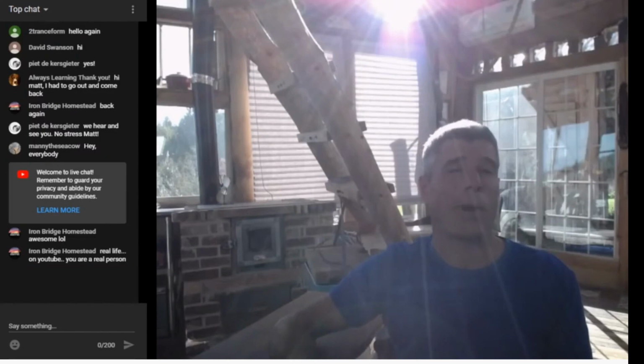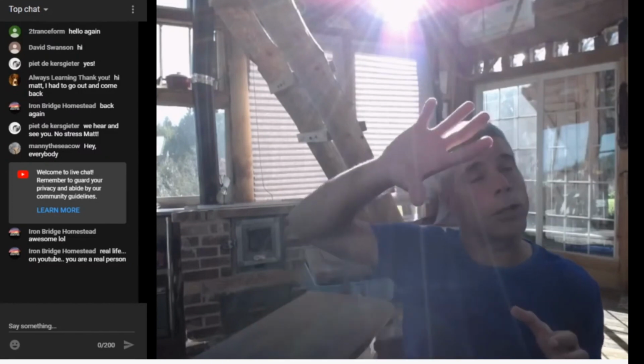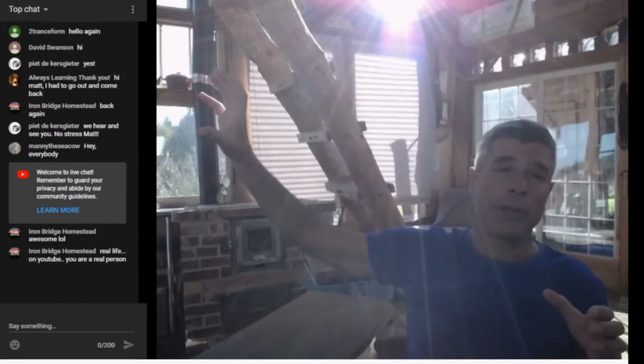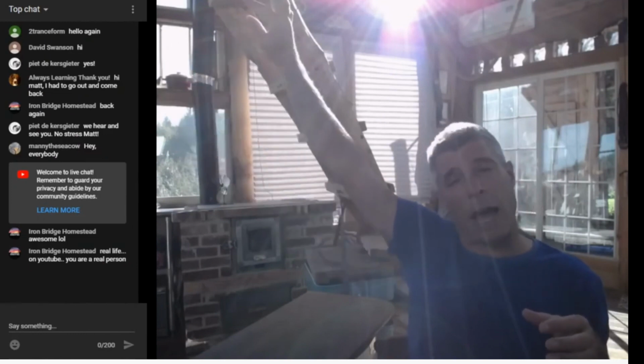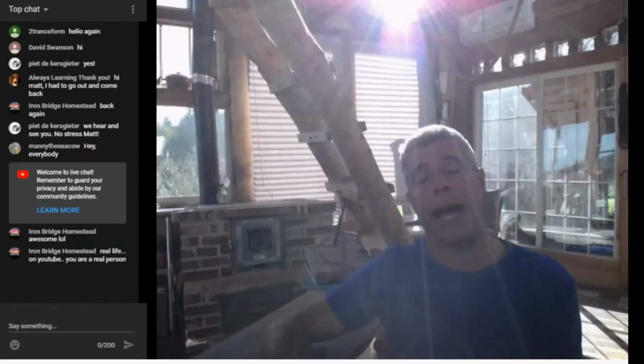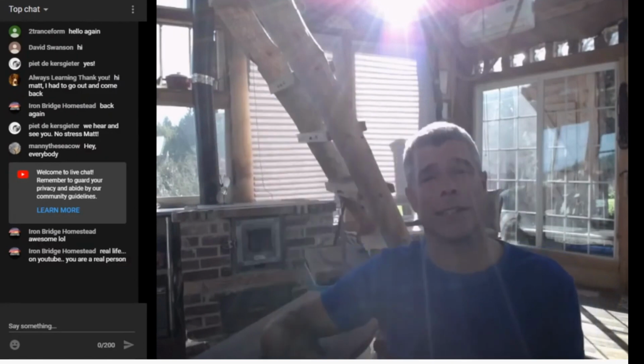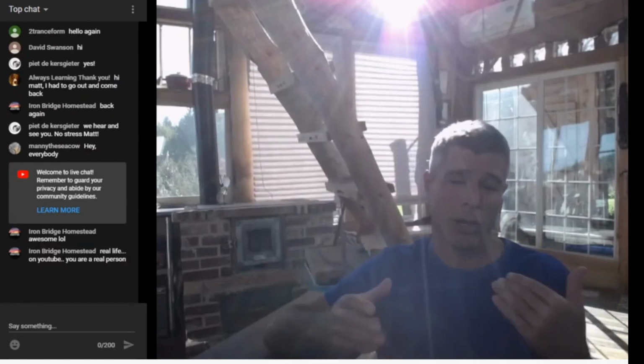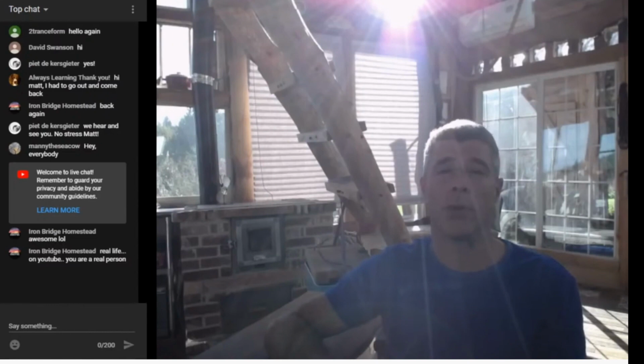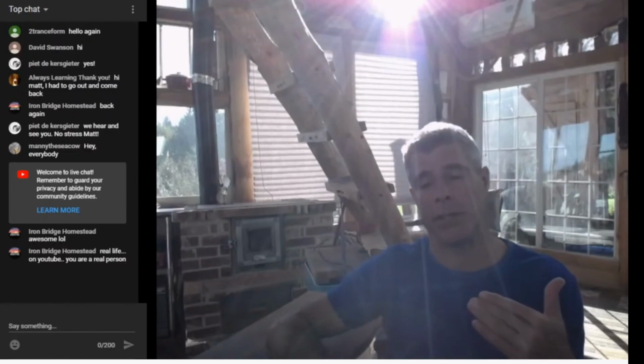Now, that isn't always possible. So it's also acceptable to go up a little bit, maybe 90 degrees sideways for just a few feet and out the wall and then up and out the outside of the building. That's typically going to be okay as well, although every little bit of horizontal chimney and every 90 does contribute to reducing your draft a little bit. So you want to eliminate as many of those as you can.